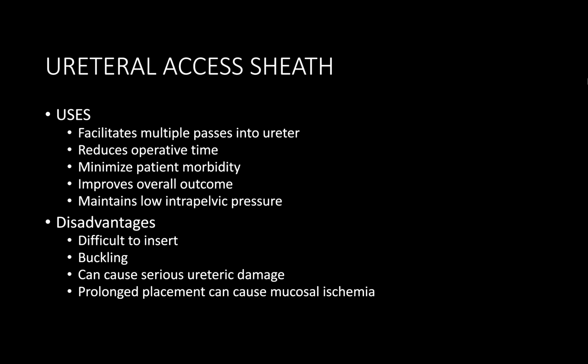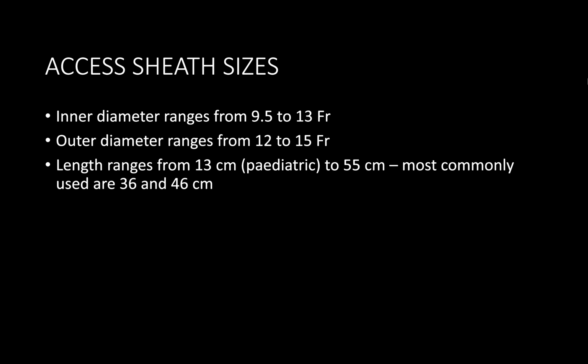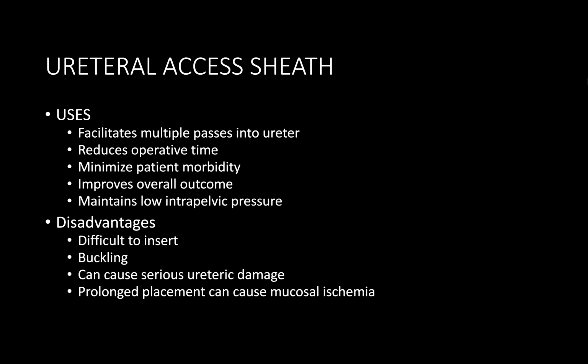This is a device that facilitates repeated passage of instruments to and from the renal pelvis, and it also reduces the intrarenal pressures during surgery. It can be between 13 to 55 centimeters long, but the commonly used lengths are 36 and 44 centimeters. It consists of an inner trocar and an outer sheath. The inner trocar has a diameter of between 9.5 to 13 French, and is the element which is inserted over the guide wire. The outer sheath has a diameter of between 12 to 16 French. It has a hydrophilic coating, and the inner lumen consists of PTFE.